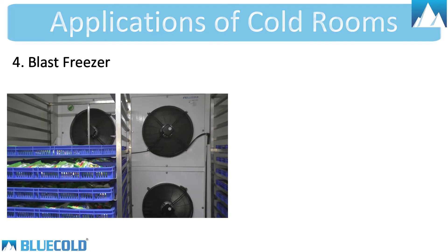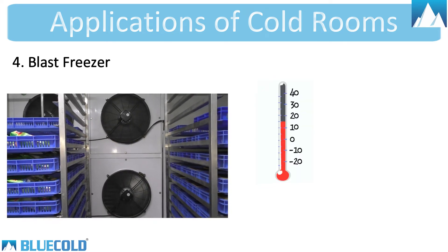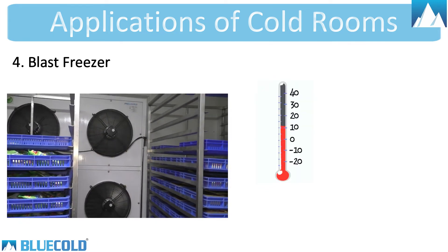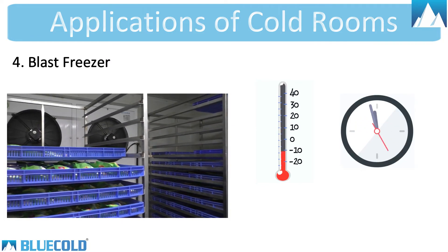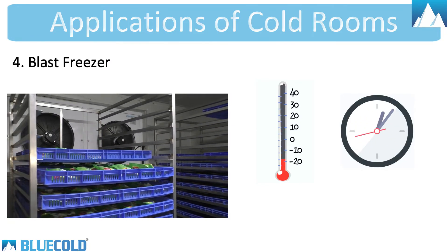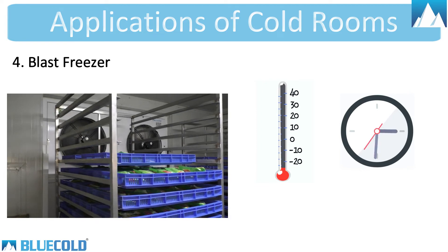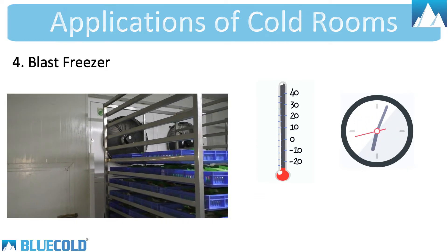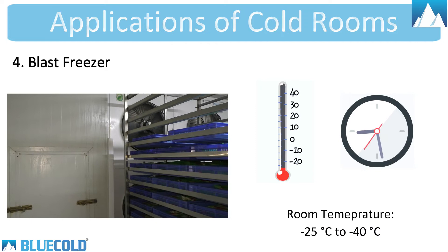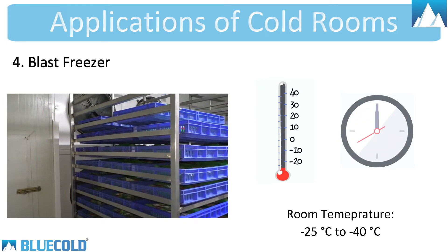4. Blast Freezer — a blast freezer is a freezer that is very cold. The idea of this type of freezer is to very rapidly bring down the temperature of foodstuffs or fresh produce, freezing them very quickly. It usually delivers temperatures from minus 25 degrees Celsius to minus 40 degrees Celsius.